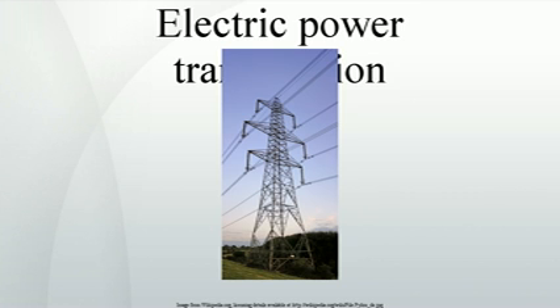High voltage direct current, HVDC, is used to transmit large amounts of power over long distances or for interconnections between asynchronous grids. When electrical energy is to be transmitted over very long distances, the power lost in AC transmission becomes appreciable and it is less expensive to use direct current instead of alternating current. For a very long transmission line, these lower losses, and reduced construction cost of a DC line, can offset the additional cost of the required converter stations at each end.